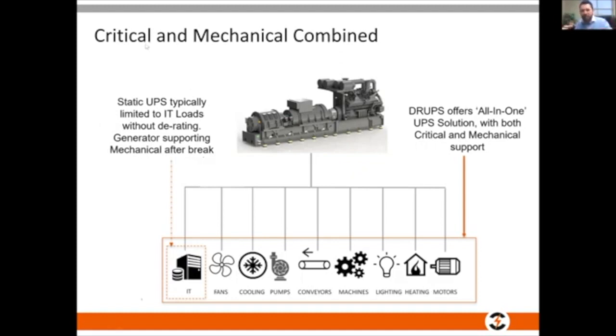What we're talking about on the slide is critical versus mechanical loads. With a Drups, you're not worried about just isolating IT. I can also cover the fans, the cooling, the lighting, the pumps, and the motors. Now don't get me wrong, I'm not saying I won't derate it. But the vast majority of applications we look at, we don't derate, because they're VFD or soft start.